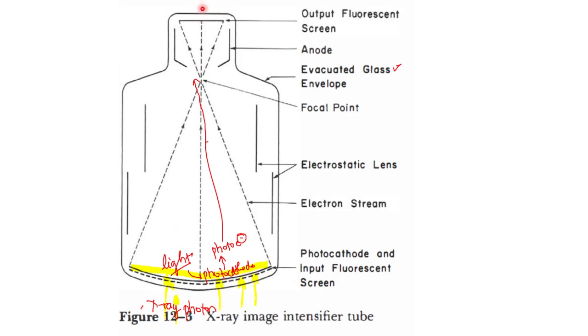These light photons carry the fluoroscopic image. When the electrons strike the output fluorescent screen, it emits light photons which contain the fluoroscopic image. So in the image intensifier, the X-ray photon is converted to a light photon, the light photon is converted to electrons, and these electrons are again converted to light photons.